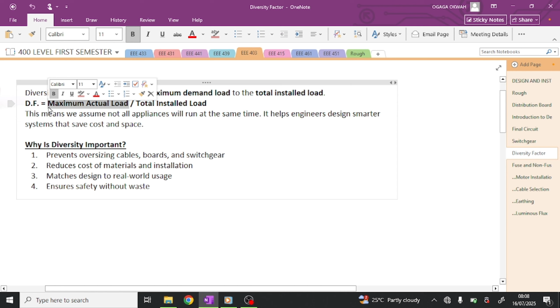Some part of the installed load, we use some parts. Your TV may be on, maybe two bulbs or one bulb and one fan, then your cooker is turned off and some other things. So the maximum actual load you make use of, divided by the total installed load, that's your diversity factor.